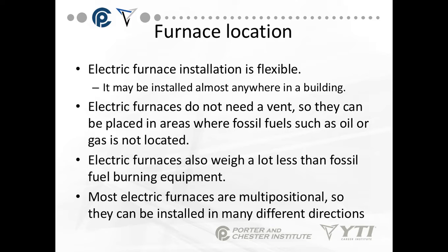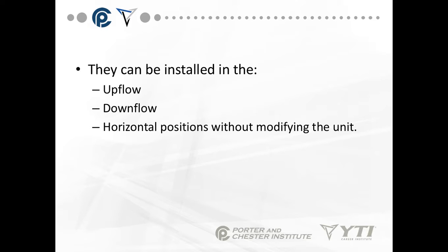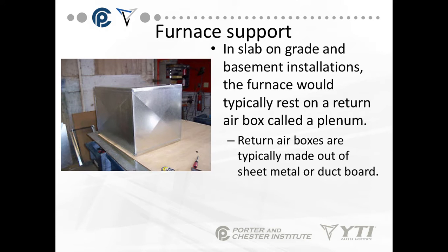I don't need to have vent connectors. I do not have to have piping for fossil fuels such as oil and gas. Electric furnaces also weigh a lot less than fossil fuel burning equipment and therefore require a little bit less support. Most electric furnaces are multi-positional, so they can be installed in many different directions of airflow. They can be installed in the upflow, downflow, and horizontal positions without modifying the unit.